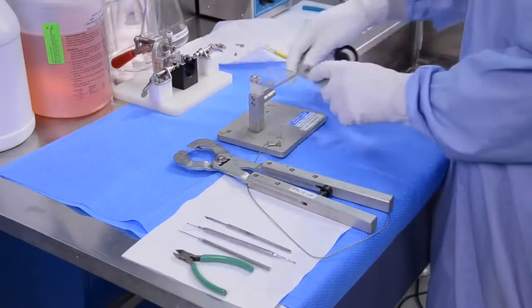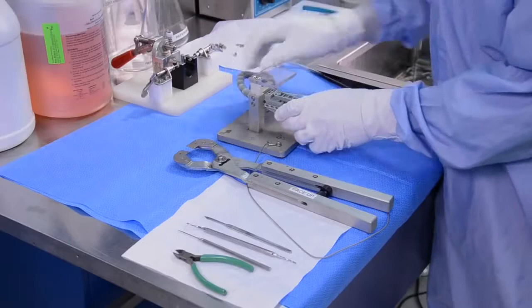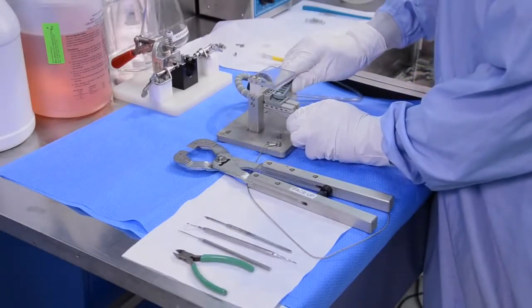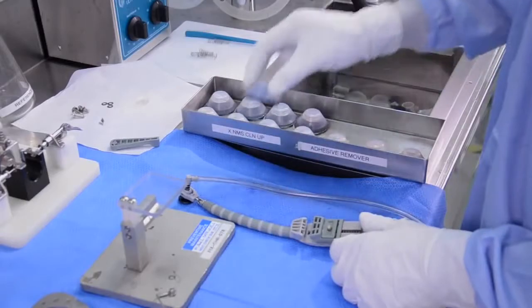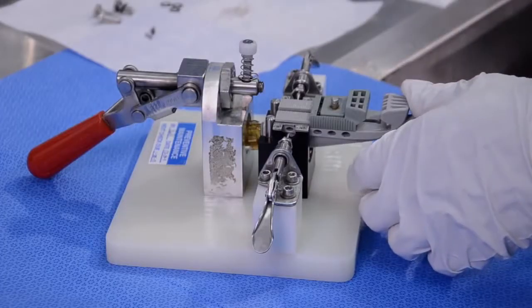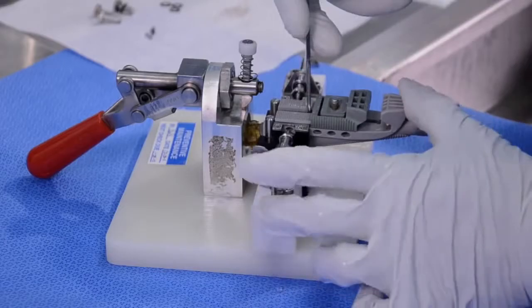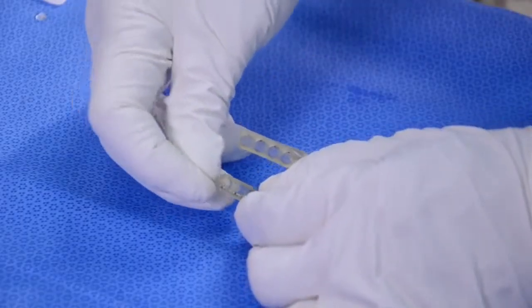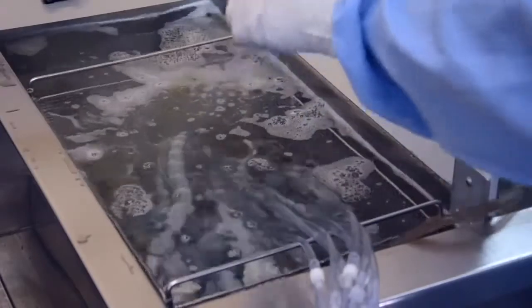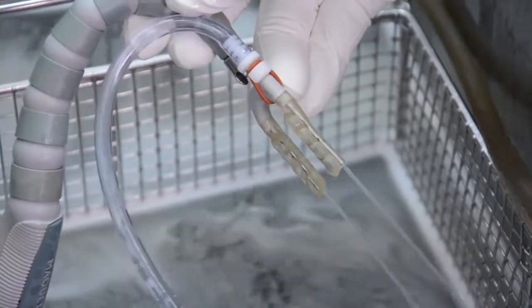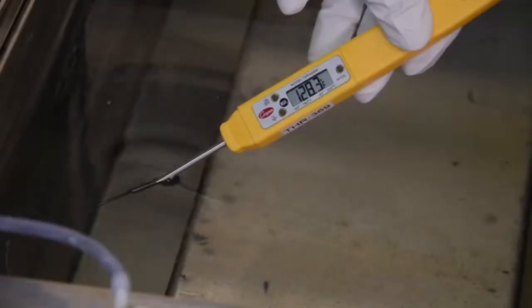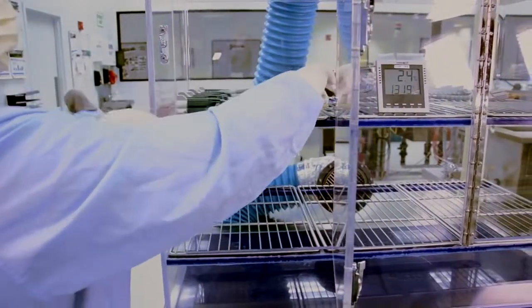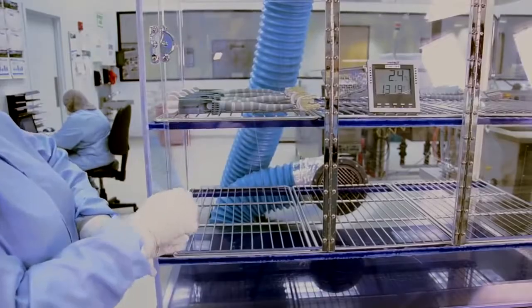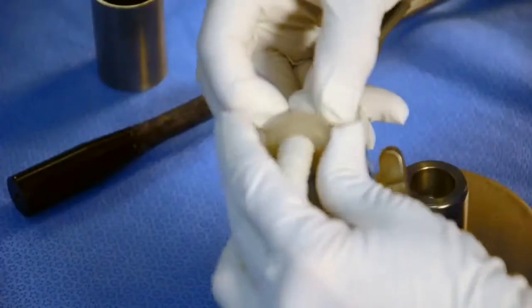Tissue stabilization and heart positioning devices are disassembled prior to being subjected to a series of enzymatic cleaning and disinfecting steps. Foam on the suction cups and all tubing is removed and discarded. Handle components are disassembled for proper cleaning, and any debris from inner lumens is removed using special brushes. Next, devices are subjected to a number of cleaning steps, including pumping with sonication for precise amounts of time and at regulated temperatures. After a final water rinse, devices are dried by vacuum under controlled temperature and humidity levels. Prior to performance testing, devices are reassembled.